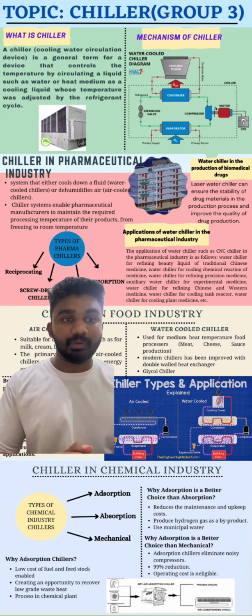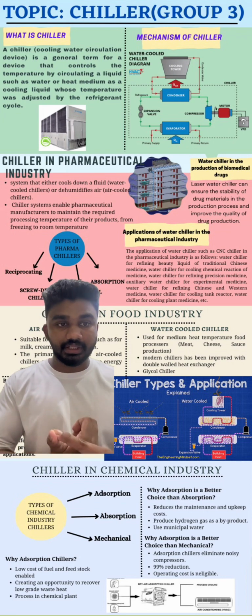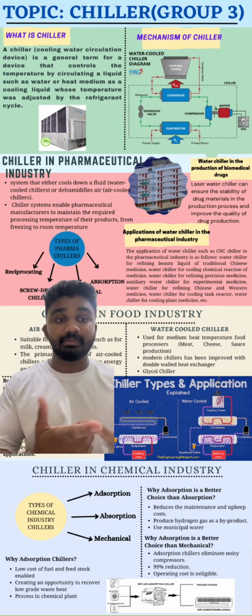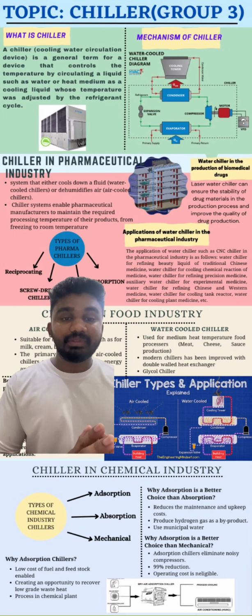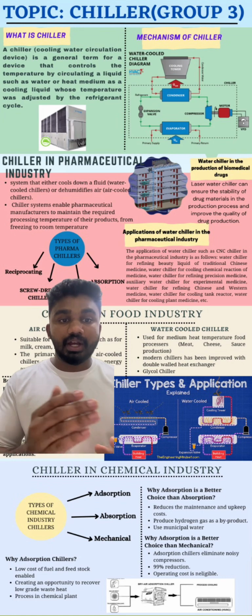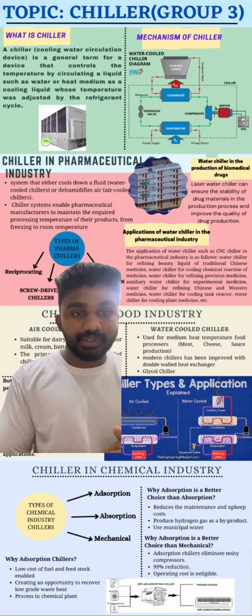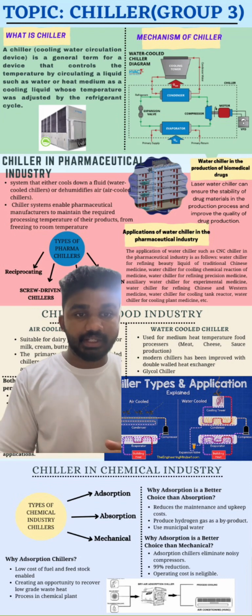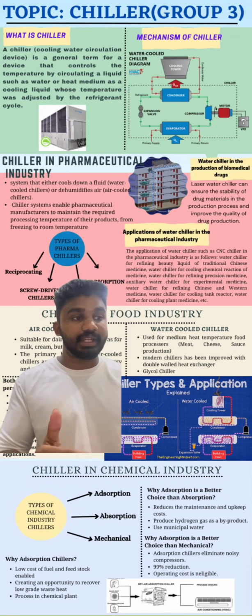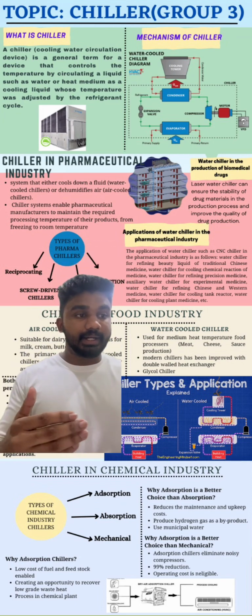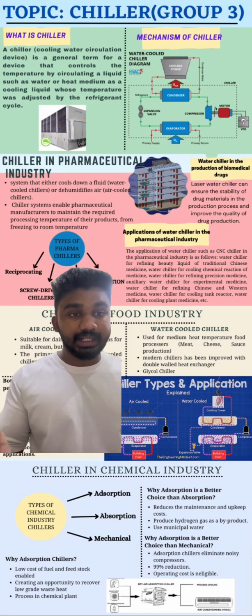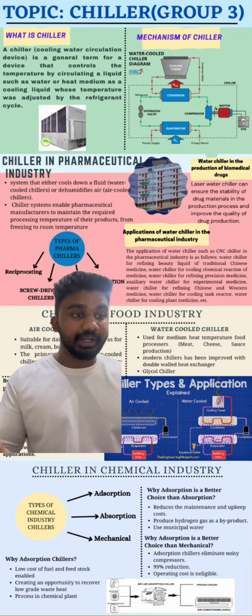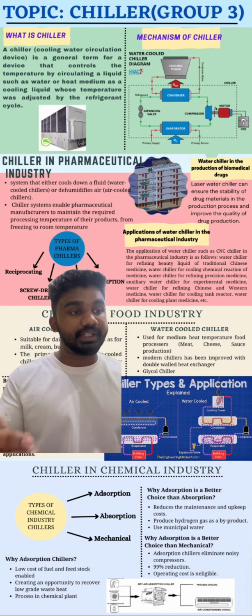There are three types. Number one, adsorption chiller. Number two, absorption chiller, and number three is mechanical chiller. From these three types of chillers, I chose adsorption. Why did I choose adsorption chillers? In the past, the low cost of fuel and feedstock enabled the chemical industry to operate mechanical chillers affordably. But today's fuel prices are creating an opportunity to recover low-grade waste heat for adsorption chillers. Energy saved adds to the bottom line.